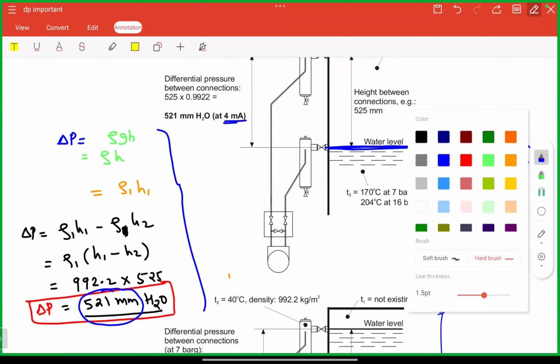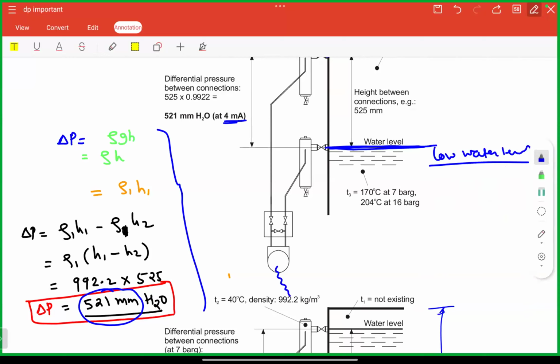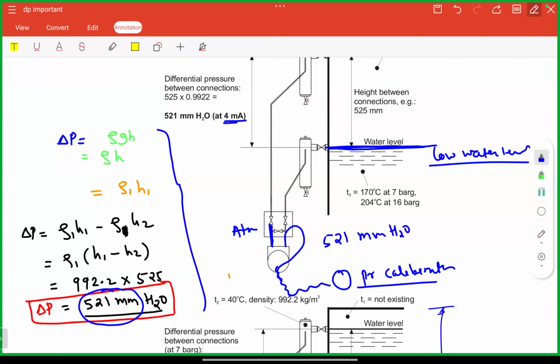So what I am going to do, I am going to connect my pressure calibrator. Okay, I am going to connect the pressure calibrator to the DP transmitter, and I am going to apply the pressure. कितना pressure apply करना है? How much pressure? One side you are going to keep it open to atmosphere. Okay. And one side you are going to connect to the pressure calibrator. And how much pressure you are going to apply? 521 mm of water column.